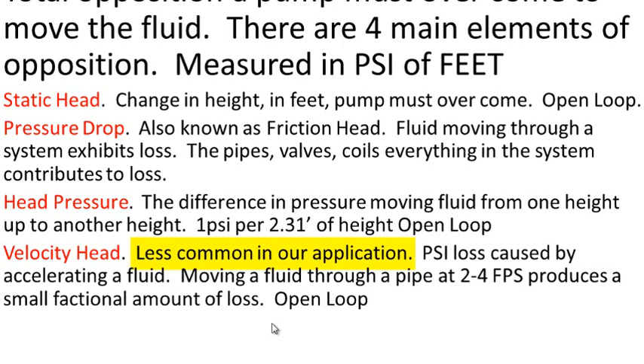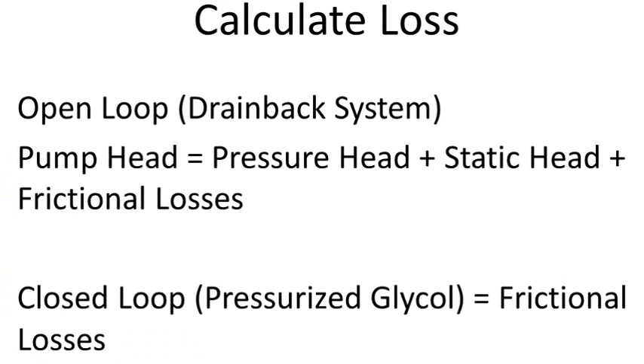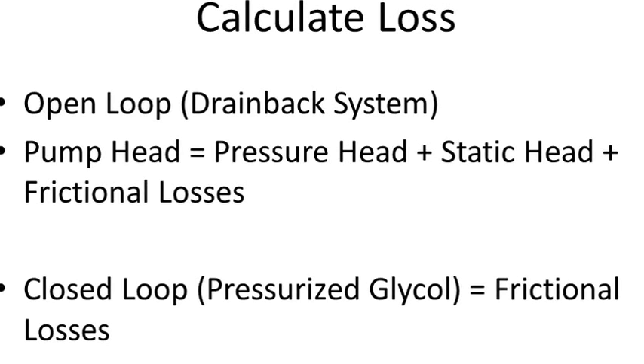Velocity head is a less common problem in our applications. Generally, in order to accelerate a fluid from stop to a certain feet per second, we lose PSI. A pump will only produce a flow — we overcome a pressure, otherwise known as pump head, in order to get that fluid to go. To calculate loss, this is simply the calculable head loss required to size the pump. We are not at this point calculating the system pressure — this is only the losses within the system to calculate for the pump. In a closed loop system, we only care about the frictional losses. In an open loop, you have all four ingredients, with the first three being the most important and velocity being ignored most of the time.